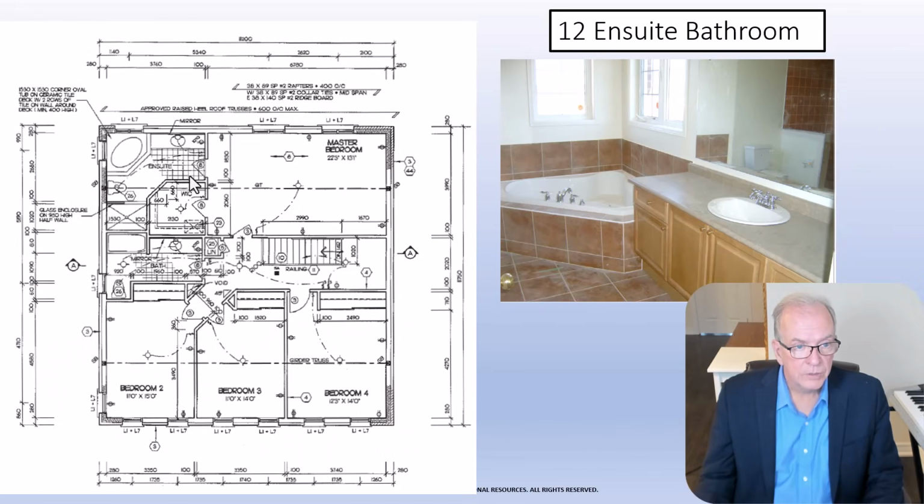Here, you can see the actual drawing pretty clearly. This is showing an outlet, and it's got a number there, 1070. Well, that's how far to put the outlet off the floor so it's above the counter. Instead, it might say 3 foot 0 inches if it was imperial, right?